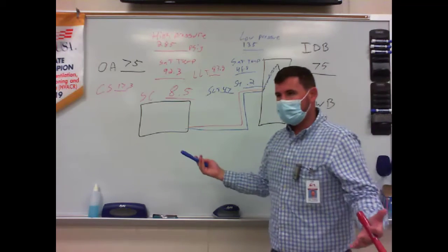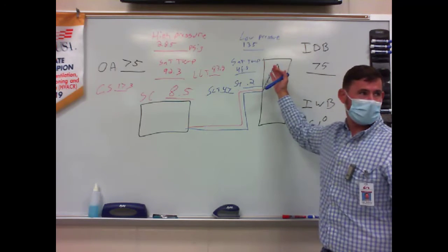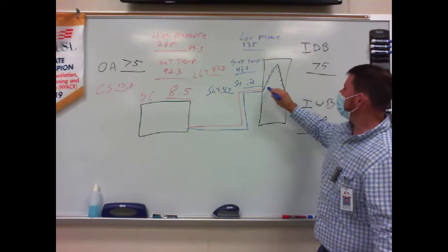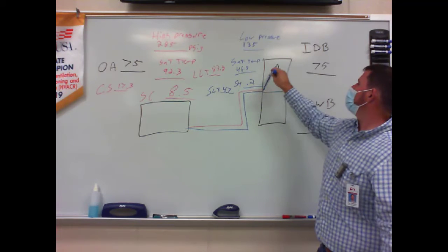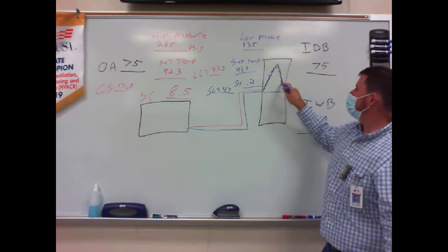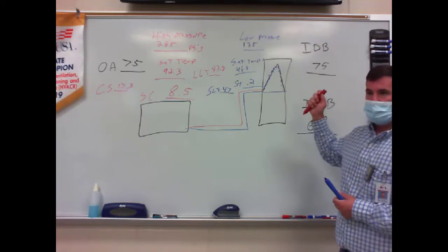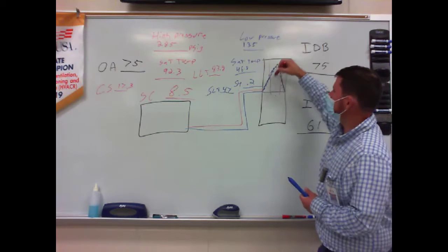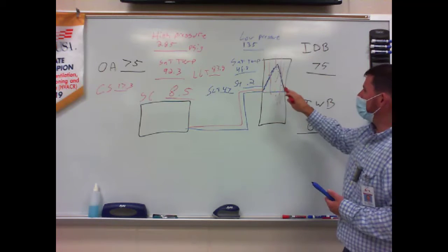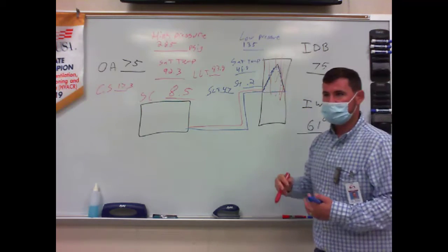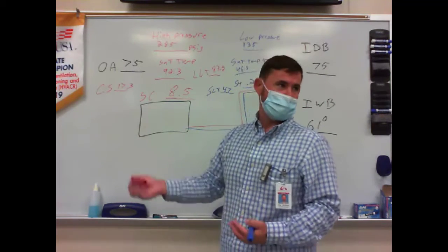Eventually, all that liquid will boil off. Our pressure is still the same through that whole evaporator, but now that liquid refrigerant that was going through here, let's say we were liquid boiling off, and maybe by here, we're all vapor. Now I'm still blowing my air across it, right? I'm still moving heat from the space I'm conditioning across that coil. So once I get to here, I still have heat hitting that vapor, but now it's going to start changing its temperature some because it's all turned into a vapor.